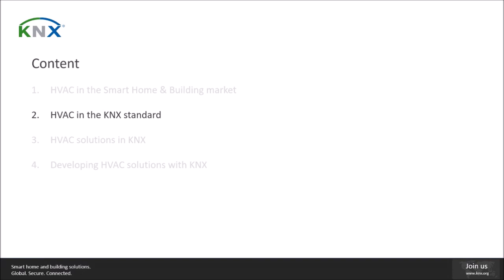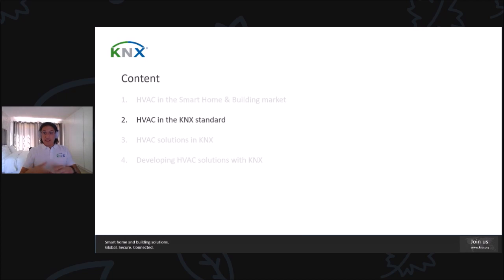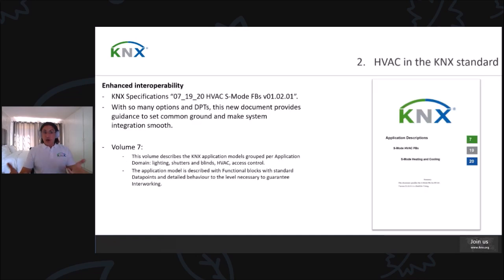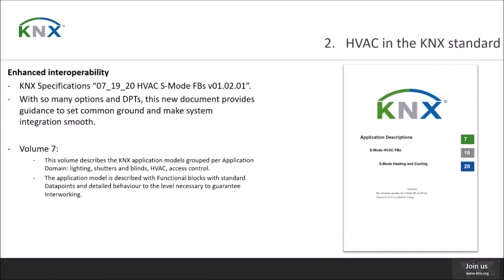Okay, that's all theory based on practical observation and current facts. Let's now look at how HVAC is present in the KNX standard. Enhanced interoperability: there is a specific volume found in the KNX specifications that deals with application domains. That's volume 7. The application models are described with function blocks that contain standard data points. This is how devices share data in a standardized way. What's the meaning of this? For instance, a thermostat can use absolute set point values, for example, 23 Celsius degrees, but it could also use shift values, given a baseline, increase set point by +1 Celsius degree.